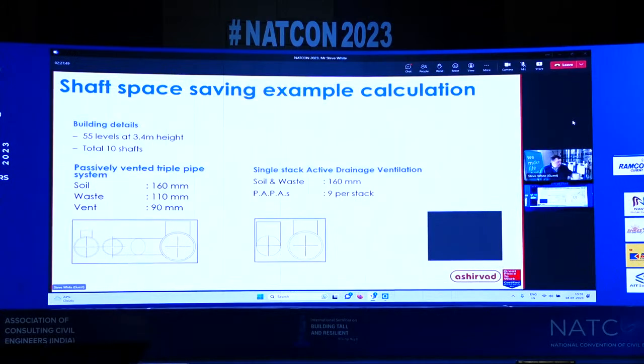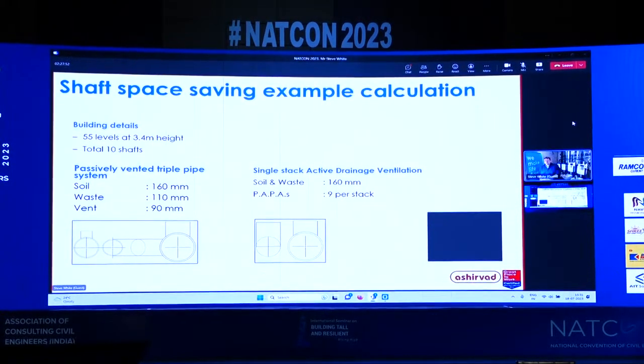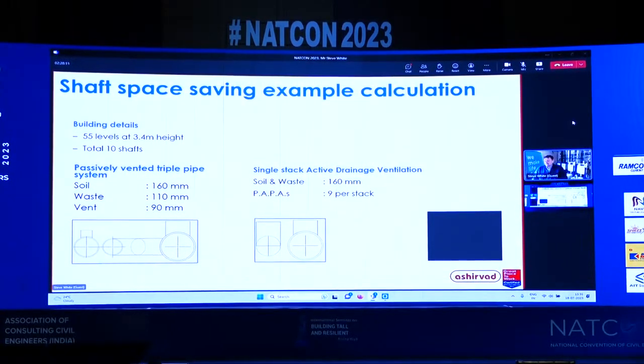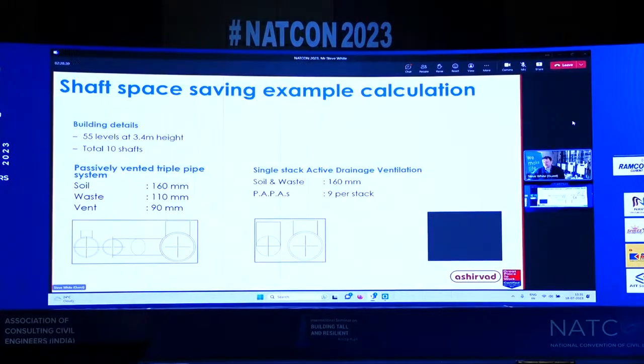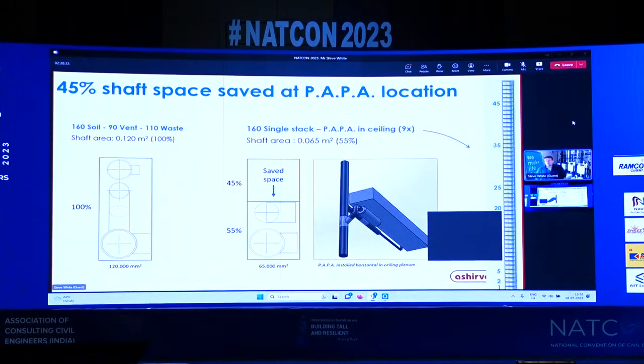So, for the architects, engineers and structural engineers, what does this mean for you? Currently in India, you use a lot of space for building services, so how much space saving does going from a 3-pipe system to a single pipe system provide for the drainage or SWR system? You can reduce the space needed to perform the same function for a high-rise building by eliminating the vent pipe, and also combining the waste and soil, or you can keep the waste and soil separate if you're treating the grey water as well. But you're eliminating the vent pipe requirements, and you're reducing the space needed for your building shaft.